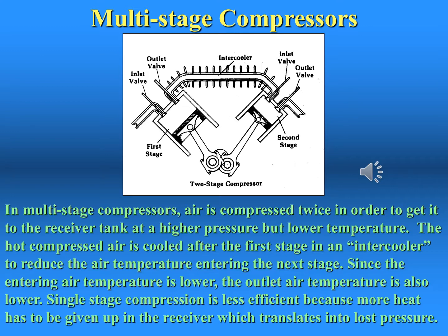As air enters the second smaller stage, it is already at a reduced temperature but a higher pressure. It is at this second stage that the air is compressed further, providing higher pressures at lower temperatures. Lower temperatures mean less loss of energy due to heat dissipation.